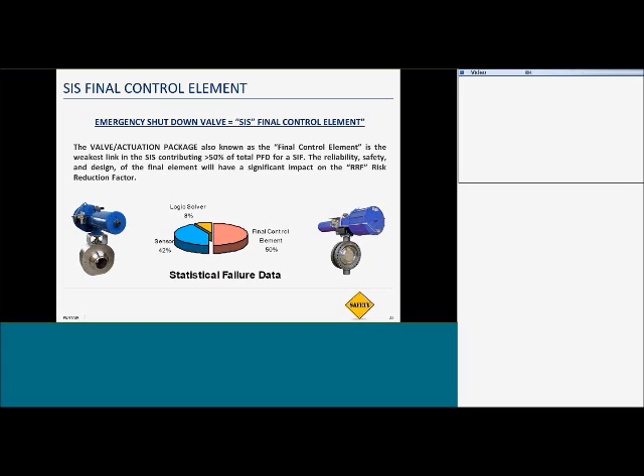Now, one of the questions I get all the time is why, as a valve and actuator OEM, are we presenting on SIS, or why are we so focused on SIS as the OEM of these components? And this slide ties this whole presentation together. When I was telling you earlier about the calculations that are done through software like SILSolver and Excellentia, where we take all of these PFD averages and we start to combine those together with the system design criteria and hardware fault tolerance, all of those calculations to arrive at the risk reduction factor, this is how those calculations are weighted.